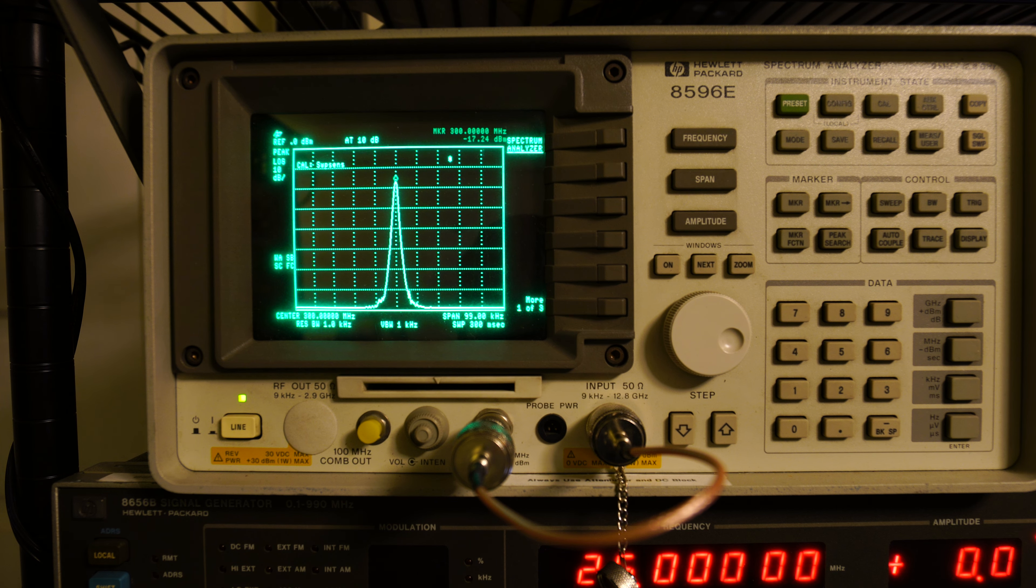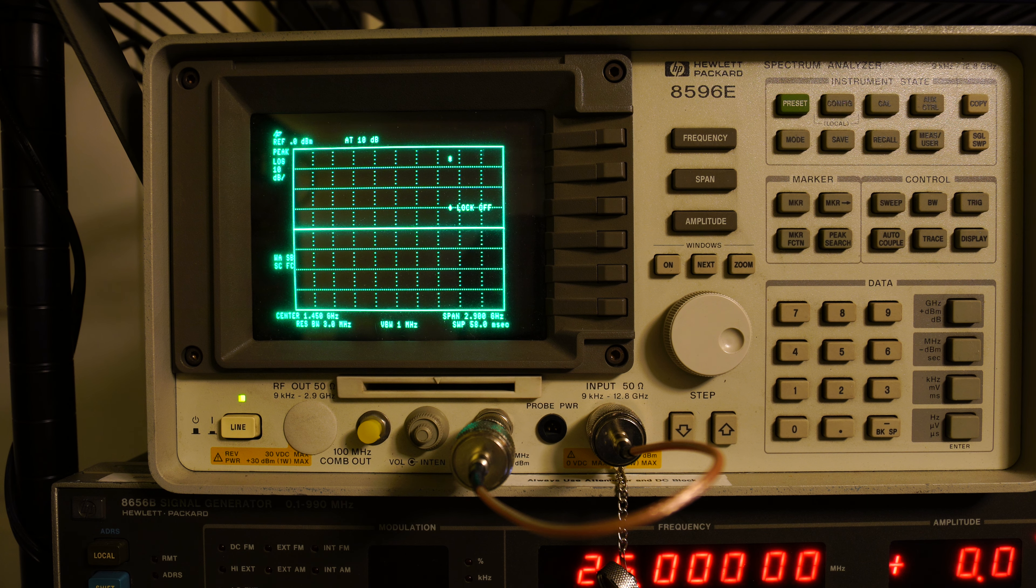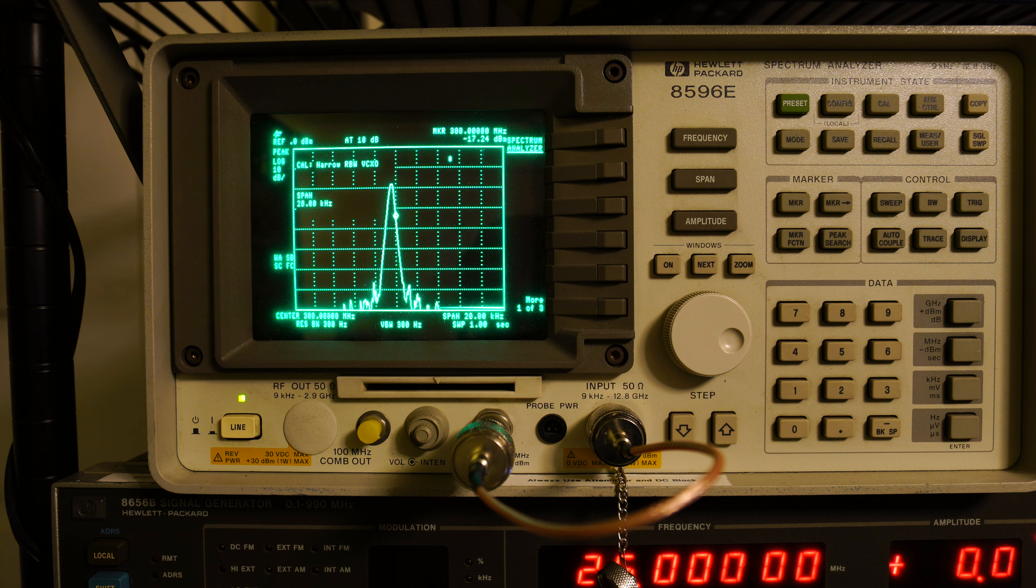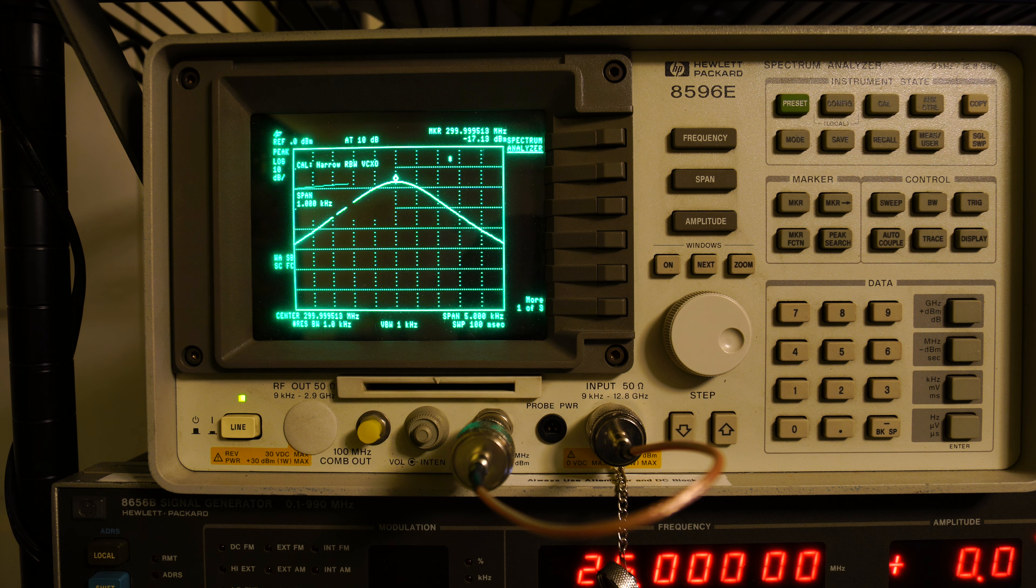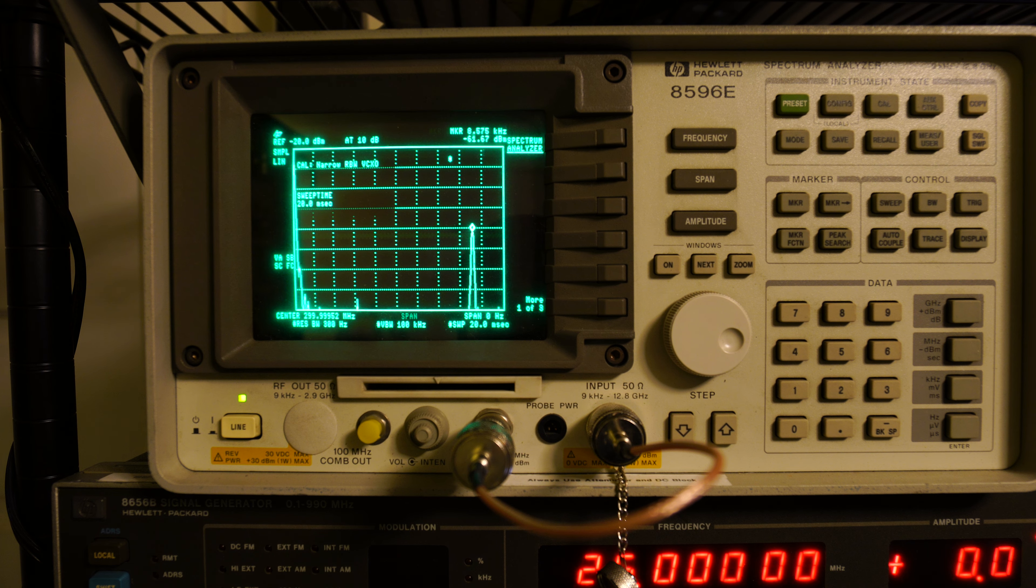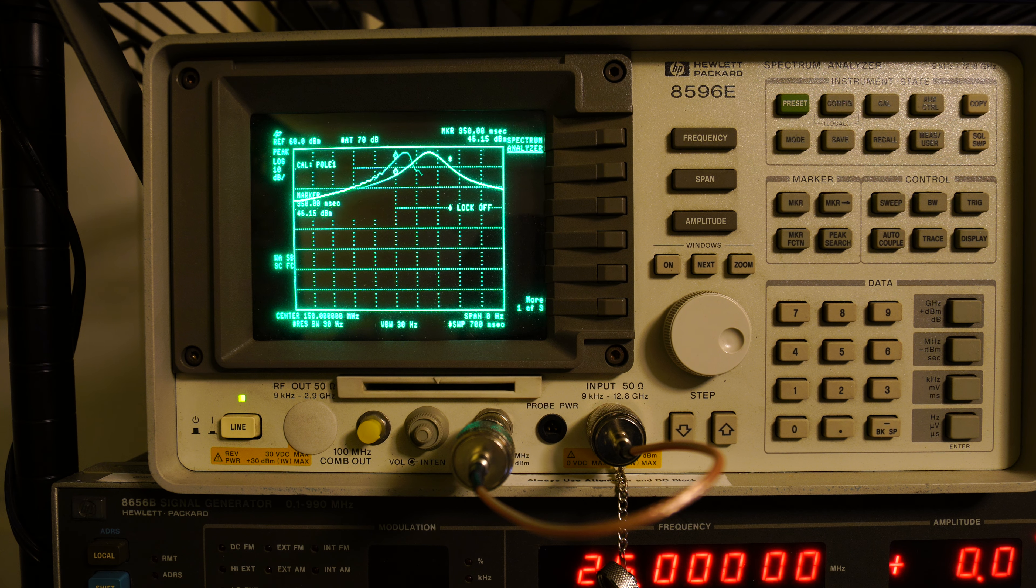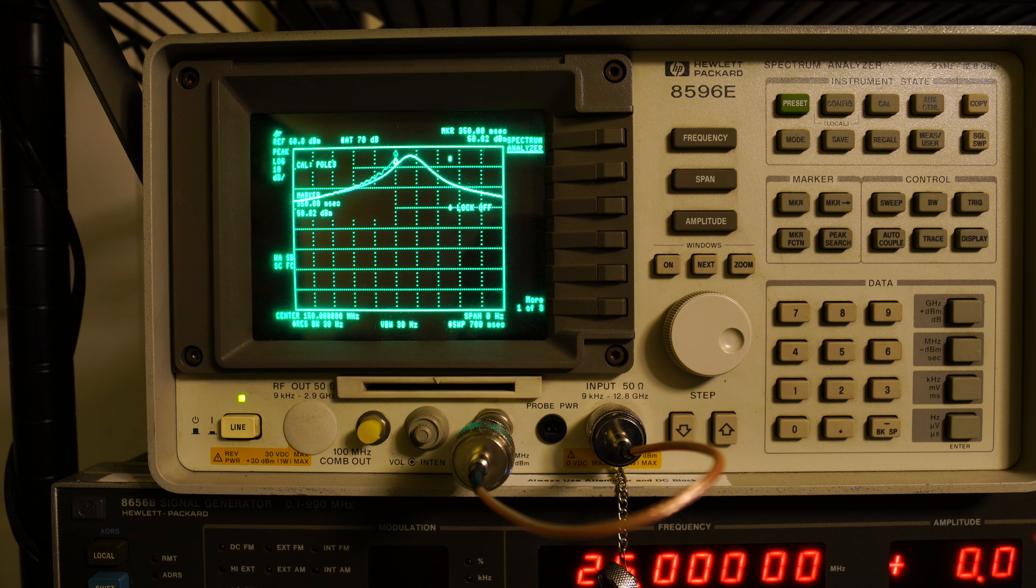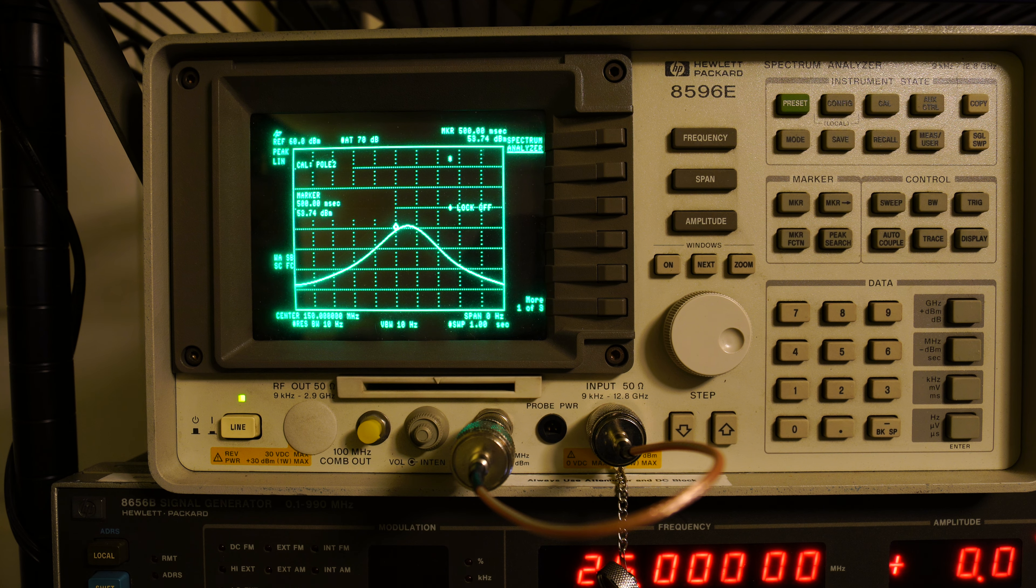And then when it gets through, it says store the results. When I tried doing this so many times before with this jumper on, I was doing the same thing except I was just doing the combination Cal Frequency and Amplitude, and I was not putting in that minus 37 Hz. That may just be a key to unlock it so that you can cal it, but they don't make that very clear.